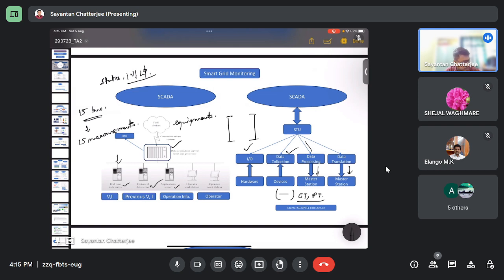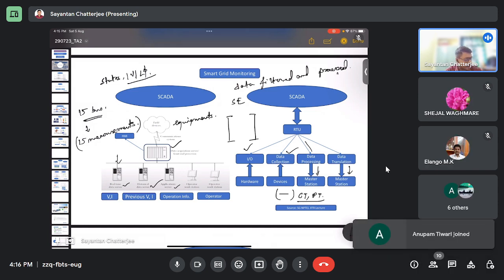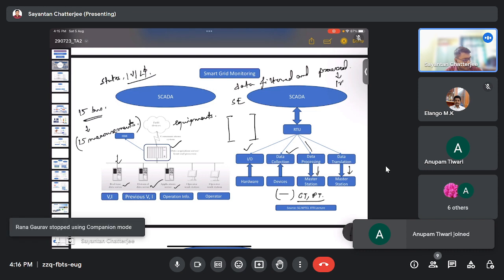So at least we will have to have 15 measurements from the RTU devices connected in the field. Based on that, we perform the state estimation where the data is filtered and processed, yielding the proper operating voltage magnitudes and the associated phase angles of the system.